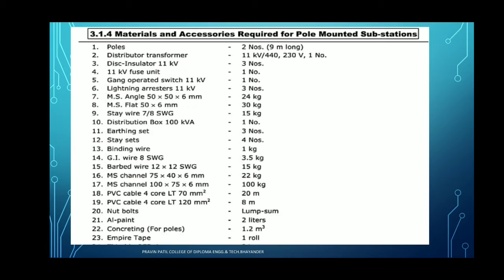Stay set, 4 stay sets are required for the distribution transformer as well as the pole mounted substation. Then binding wire, 1 kg of binding wire may be required. GI wire with SWG, 3.5 kg or 4 kg may be required. Then barbed wire of 12 by 12 SWG may be required, 15 kg. Then MS channel 75 by 40 by 6 mm, with a weight of 22 kg.